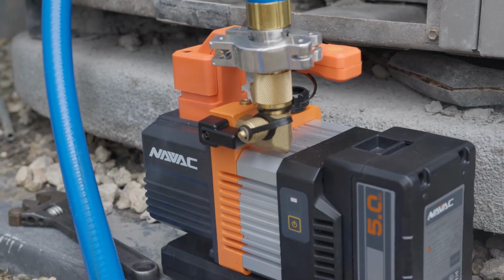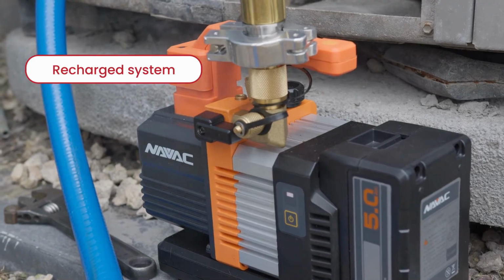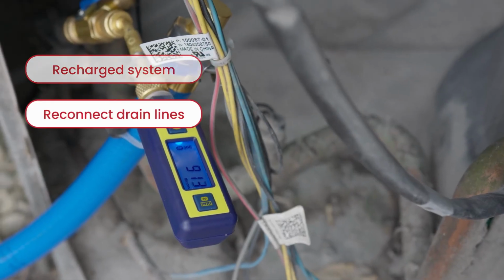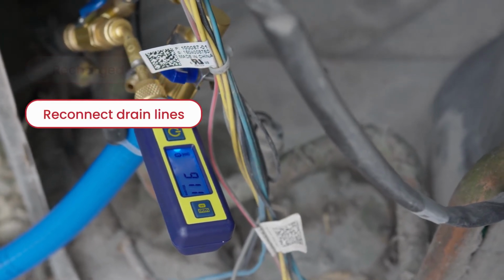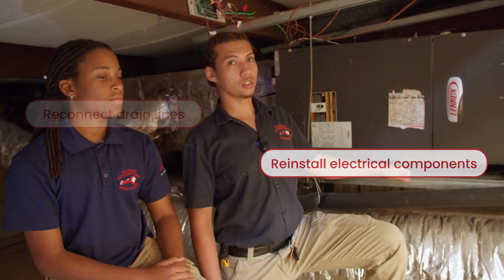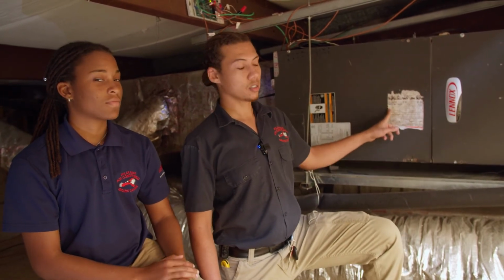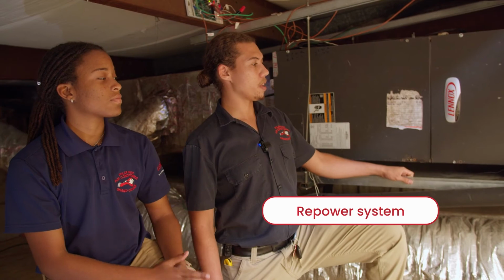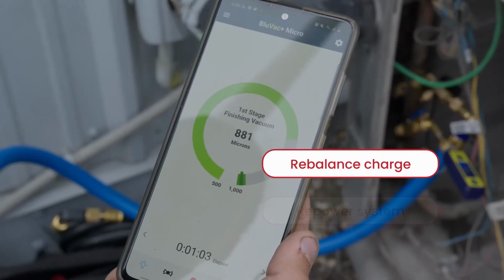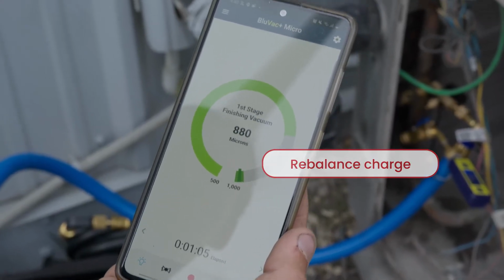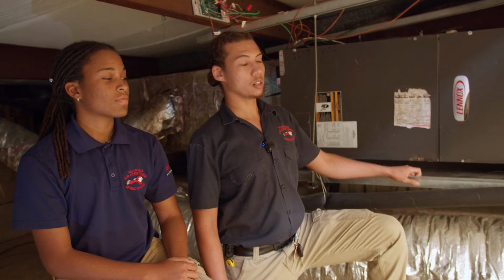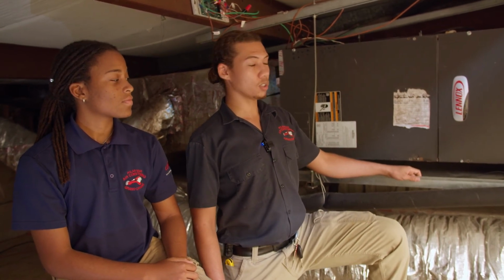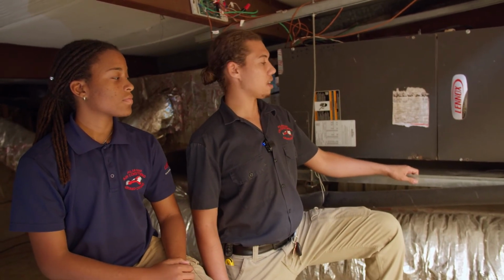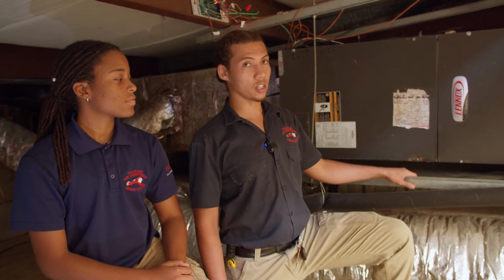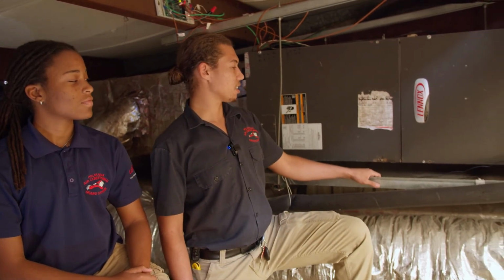A really good vacuum was pulled on the system. We recharged the system with refrigerant, reconnected the drain line, reinstalled all electrical components, including the blower wheel, repowered the system, balanced the charge back to manufacturer specifications, and we've tested the unit down to a temperature of 68 degrees at the thermostat to ensure that it's no longer condensating. And as you can see, it's completely dry.